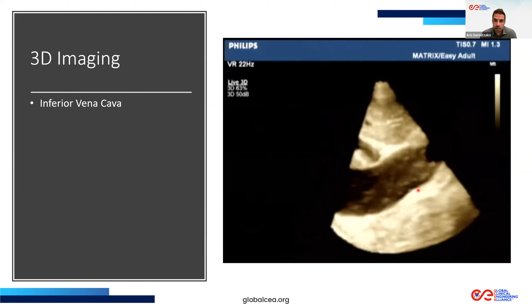Now, as we said, ultrasound imaging also gives us the great advantage of being able to image the blood flow. How do we do that? We do that based on the Doppler effect. The Doppler effect is just the effect that when an echo is coming back from a moving object, it will have a phase shift depending on the direction and the speed of the moving object. So the moving object here is the blood. We get this frequency shift, we calculate it, and then we are able to understand the direction and the speed of the blood.